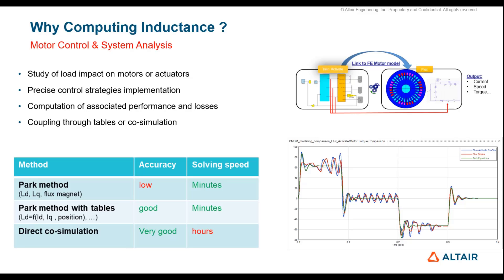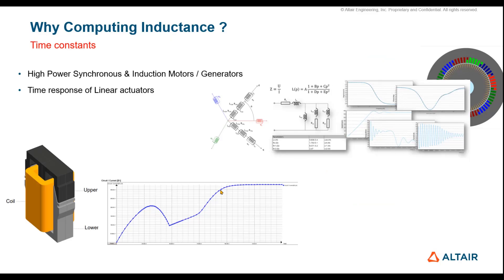For a permanent magnet machine, for instance, we have a Park model — a simplified Park model defined with Ld and Lq. So we need this Ld/Lq computation. Or we can use a reduced order model using lookup tables, which is more accurate. If we compare these two methods to a direct co-simulation, which is possible with Activate and Flux, this direct co-simulation is the most accurate but the solving time is hours, not seconds or minutes. The best compromise between computation time and accuracy is using the lookup table.